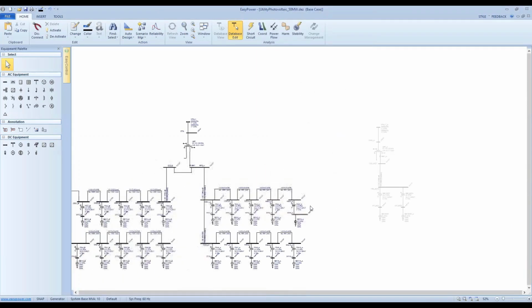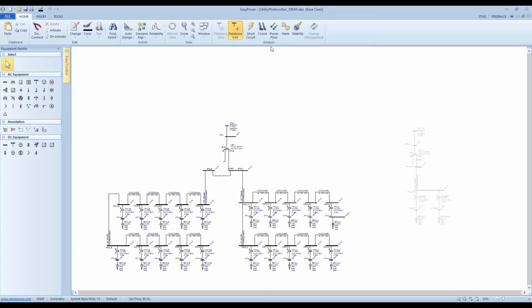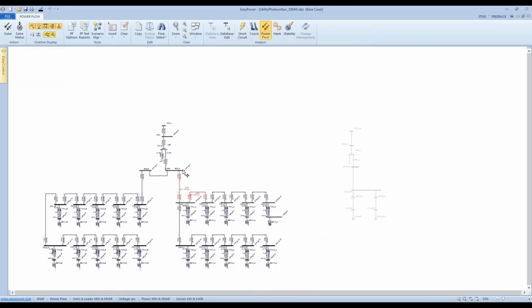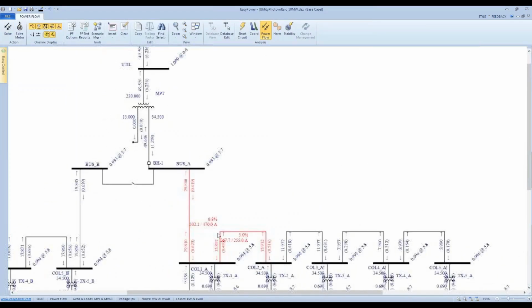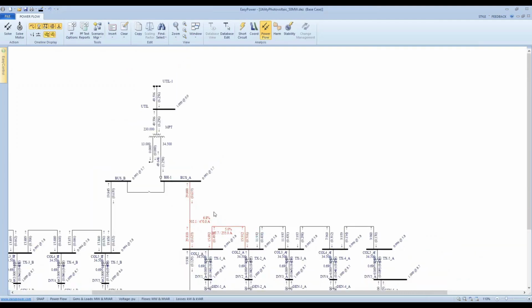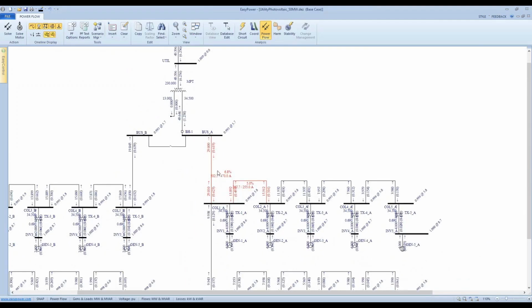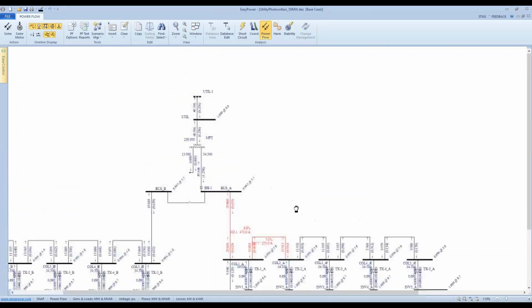So let's compare the performance. For a 50 megawatt design, let's run the power flow first. Run the power flow. Please forgive me, I didn't change the design at all. I keep the same impedance and rating for the sake of comparison, or for the sake of easement of changing the turbine size. In real life, if you change your inverter size, definitely the collector circuit needs to be changed, right? That's a very natural thing.